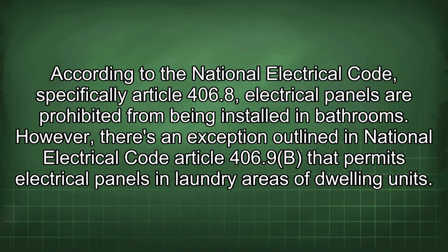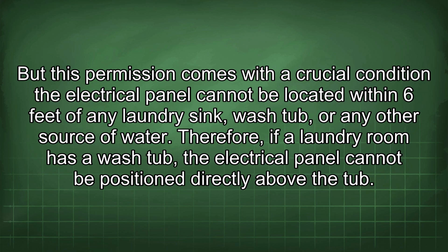According to the National Electrical Code, specifically Article 406.8, electrical panels are prohibited from being installed in bathrooms. However, there's an exception outlined in National Electrical Code Article 406.9b that permits electrical panels in laundry areas of dwelling units. But this permission comes with a crucial condition: the electrical panel cannot be located within 6 feet of any laundry sink, wash tub, or any other source of water.